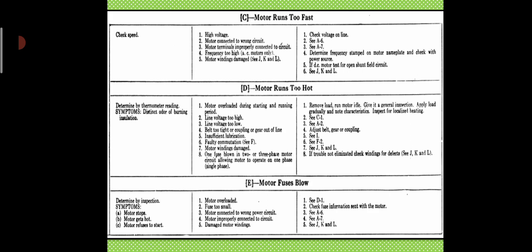Now, motor runs too hot. Determine by thermometer readings. The symptom is a distinct odor of burning insulation. The causes are: motor overloaded during the starting or running period, line voltage too high, line voltage too low, belt too tight or coupling or gear out of line, insufficient lubrication, faulty connections, motor windings damaged, one fuse blown in a two or three phase motor, circuit allowing motor to operate on one phase. Remove load, run motor idle, and give it a general inspection. Apply load gradually and note the characteristic. Then adjust belt, gear or coupling. If trouble is not eliminated, check windings for defects.